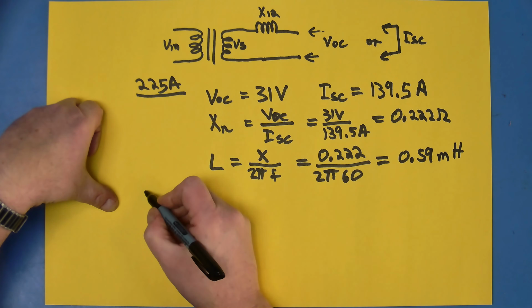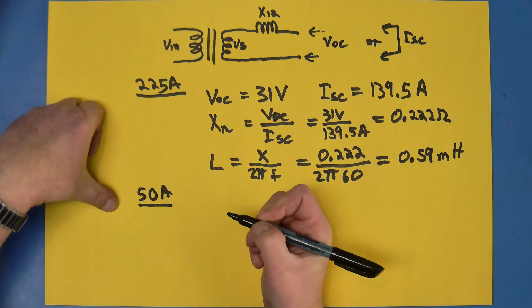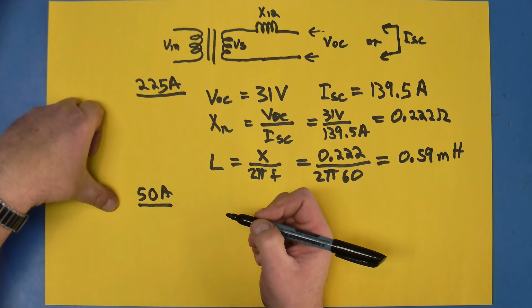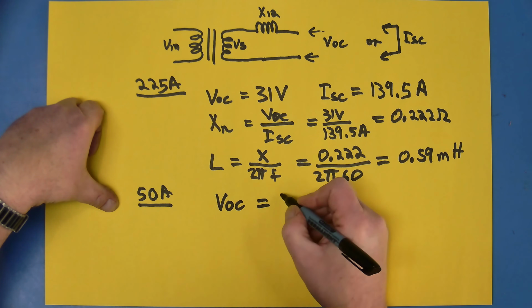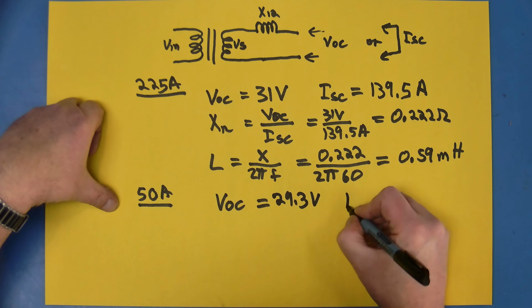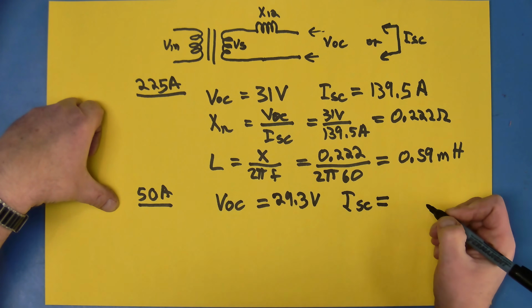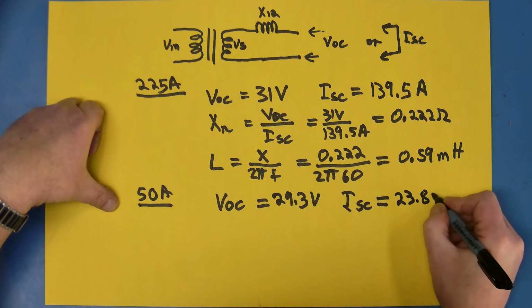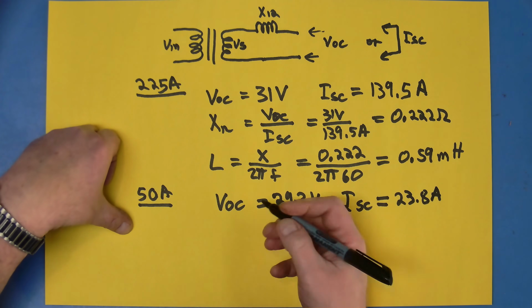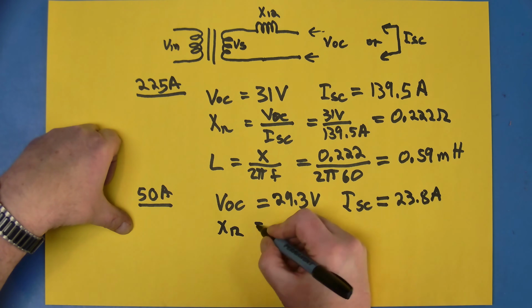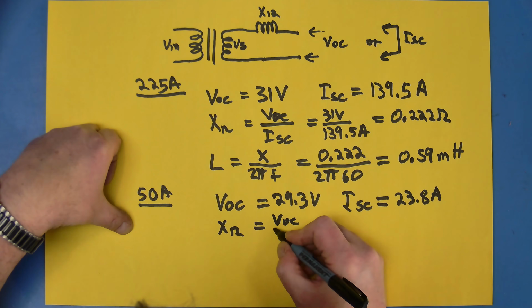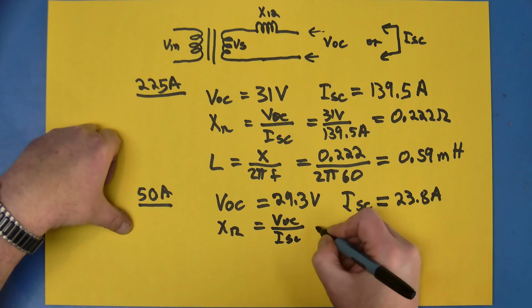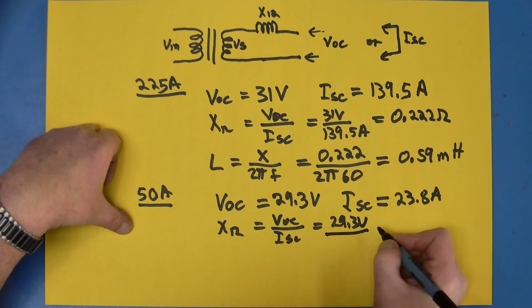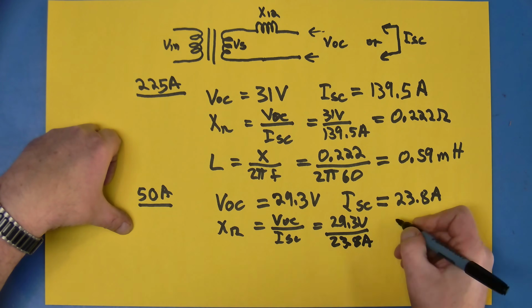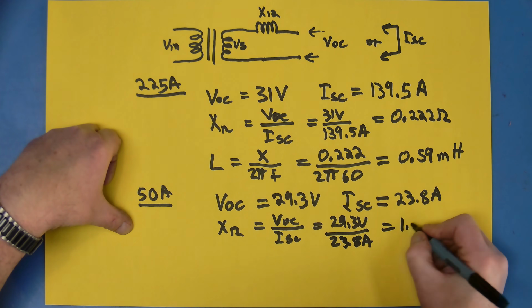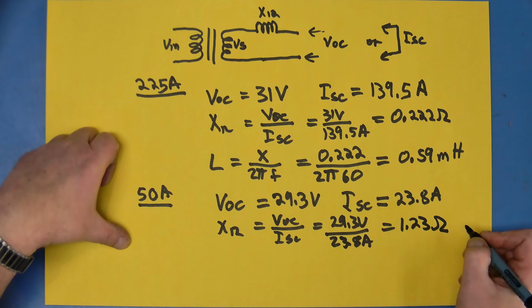What do we get if we do the same thing for 50 amps? At the 50 amp setting, we recorded an open circuit voltage of 29.3 volts and a significantly lower short circuit current of 23.8 amps. Now we can do the same calculations. The reactance is the open circuit voltage over the short circuit current, which equals 29.3 volts over 23.8 amps, resulting in a reactance of 1.23 ohms.